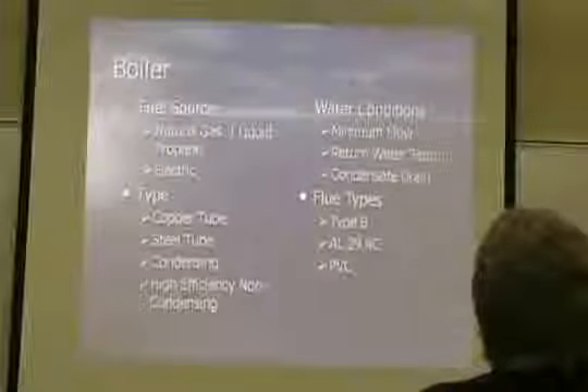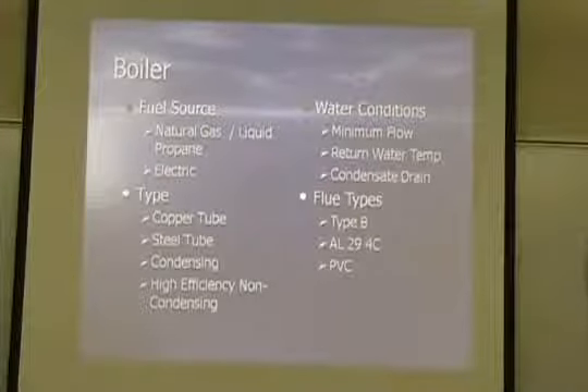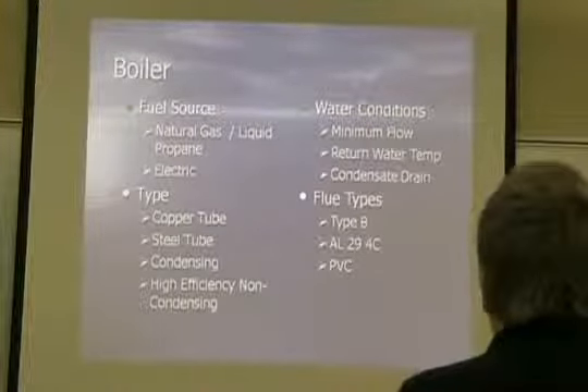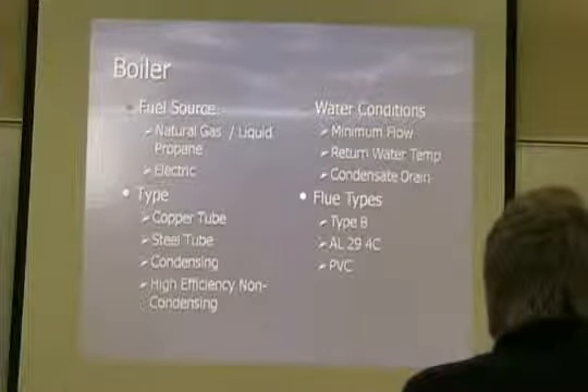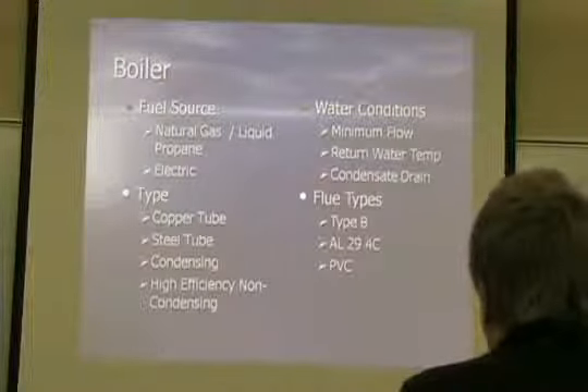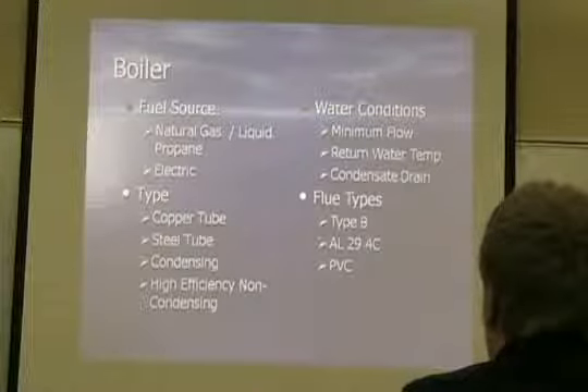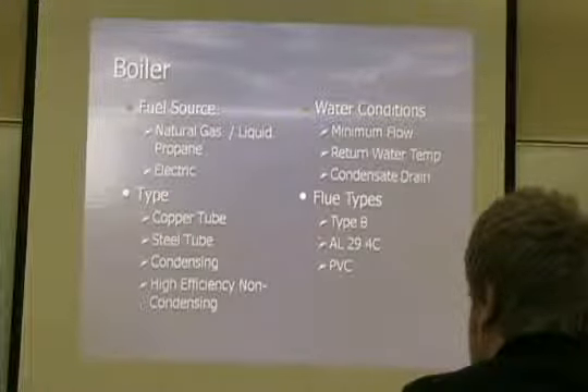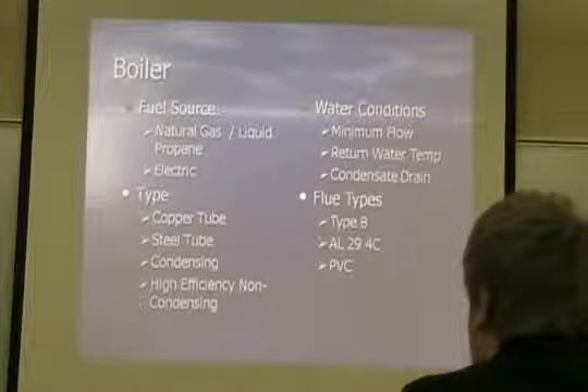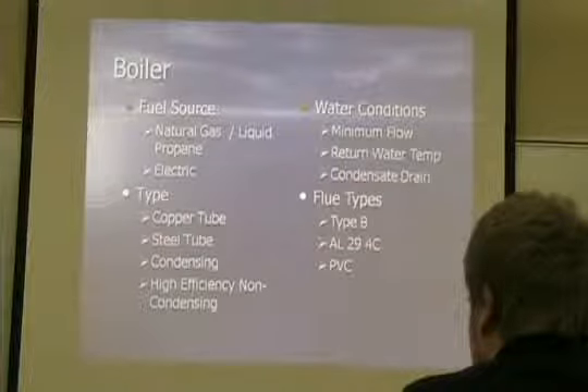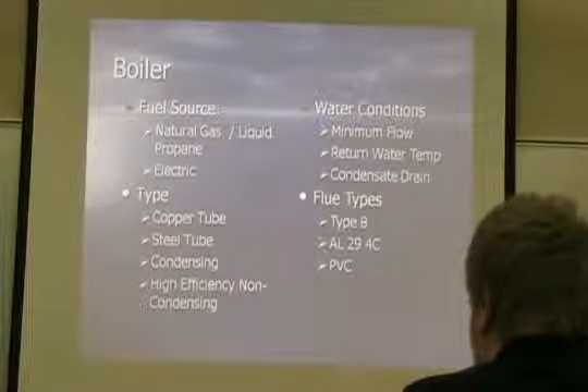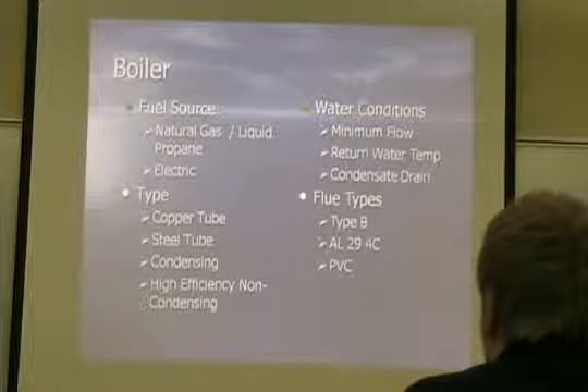Boilers are used for the heat of absorption. I'll show you how we implement the boiler, but any kind of boiler we use: gas, propane, electric, copper tube, steel tube, condensing. Probably the best application is that condensing boiler that we can operate at very low water temperatures. If we don't use a condensing boiler, you have to be very concerned with how you connect your piping up to the boiler, because any water temperature less than 140 degrees in that boiler is going to cause sweating unless it's a condensing boiler. But there are ways to get around that. What to do is bypass some of the supply water to the return water and bump the return water temperature up.